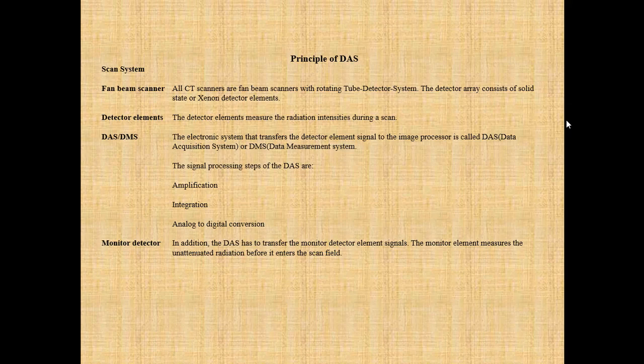Principle of the DAS scan system: all CT scanners are fan beam scanners with a rotating tube-detector system. The detector array consists of solid state or xenon detector elements that measure radiation intensities. During a scan, the DAS or DMS is the electronic system that transfers the detector element signals to the image processor. Signal processing steps of the DAS include amplification, integration, analog-to-digital conversion, and the monitor detector.